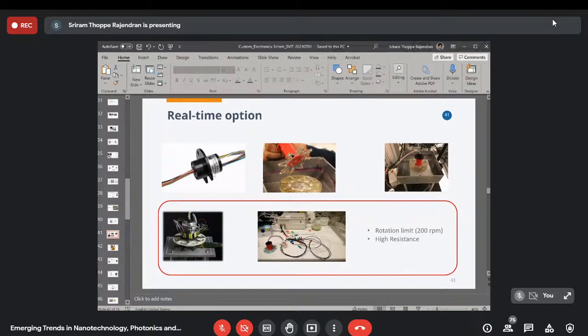So there are devices called slip rings, which are rotating connectors. You put them on top of the disk platform like this, and the connectors go towards the potentiostat while the disk is spinning. So that's how it looks in terms of the wiring. This is one type of slip ring, and this is another type of slip ring connected to the disk. This disk has 8 detection units, and each detection unit has a reference, counter, and working electrode. 3 electrodes, so 3 into 8 is 24. There are 24 contact points on this disk, and then you have 24 contact points of connectors to the machine. So you need to make 48 connections.